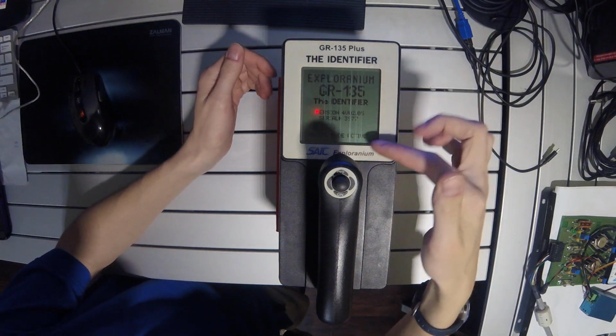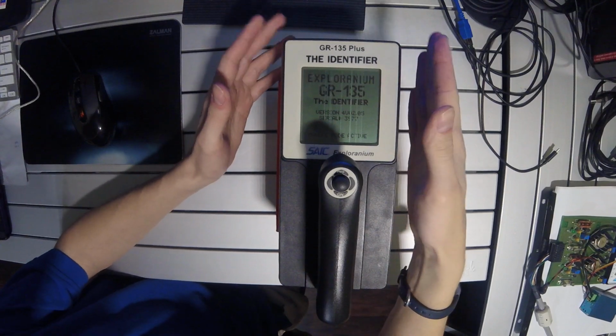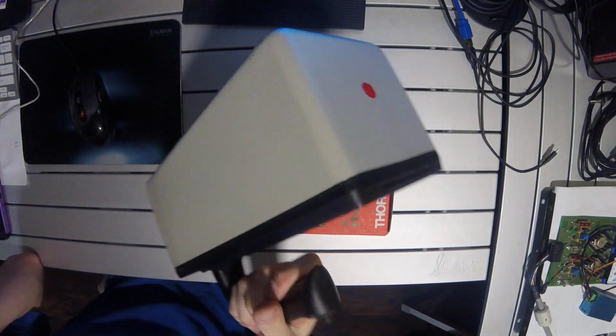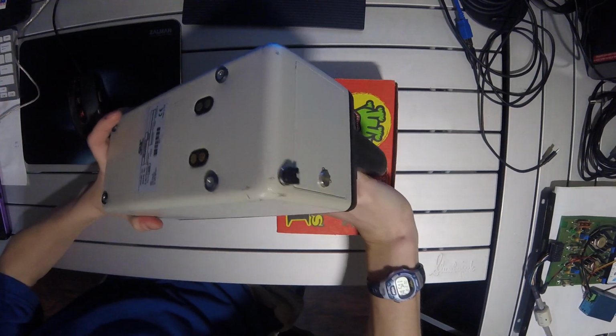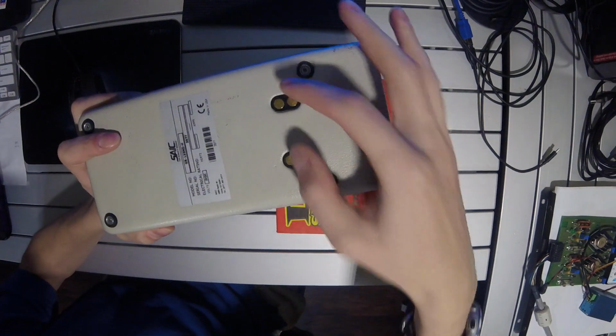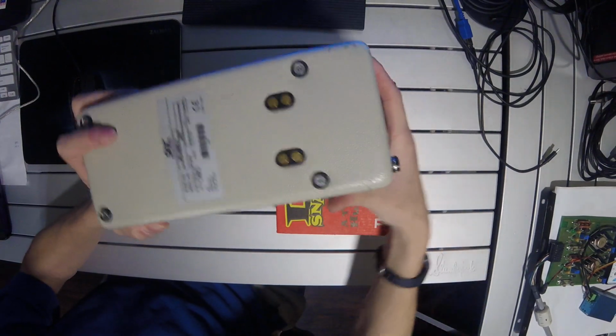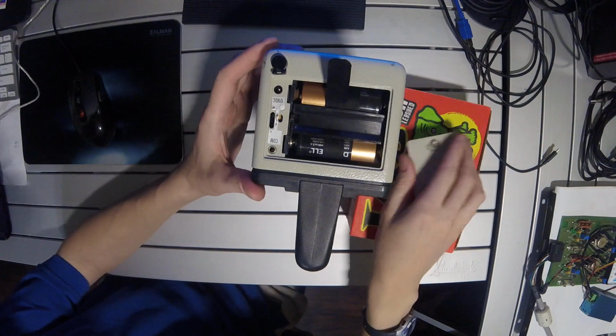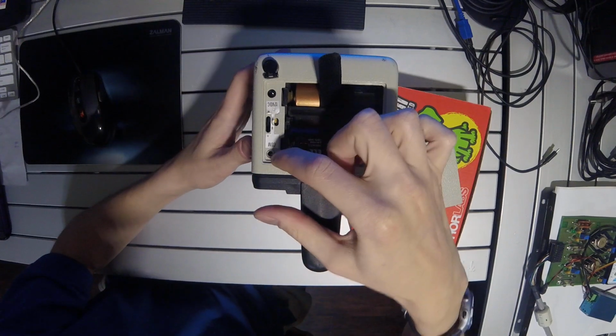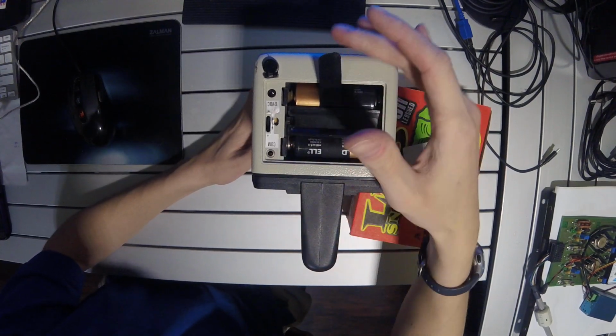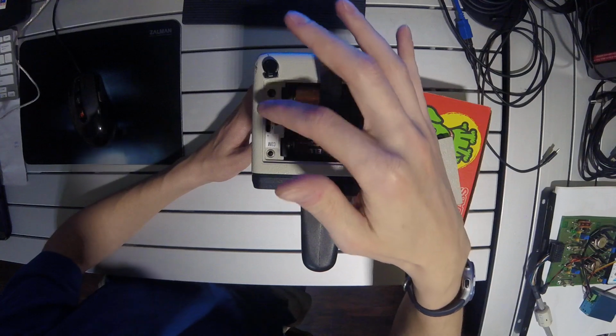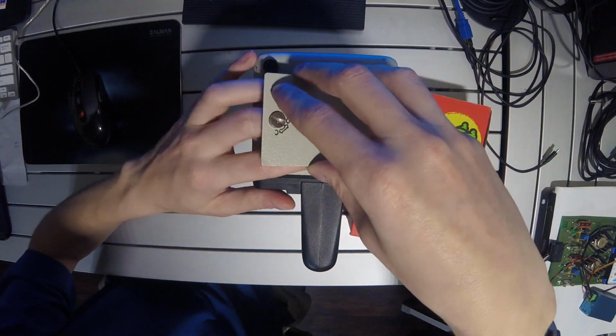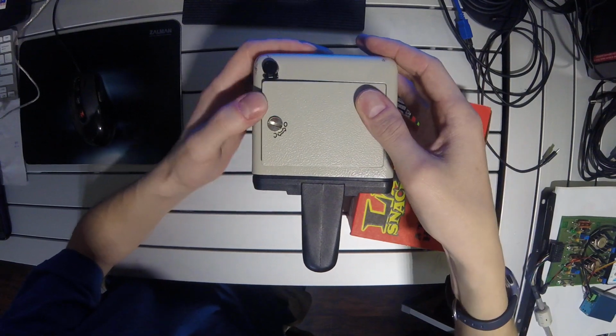As you can see, it has some dead lines, which is common for the older GR-135 units. It's a portable handheld unit, which is ruggedized and battery-powered. It has contacts for a docking cradle for power and serial communications, and it also has a serial communications port in the backpack, in the battery pack. So there's a TRS jack here for plugging in a remote serial port, as well as an external 12 volts DC for external power, and a mode switch for automatic and manual mode. Right now it's set up in manual mode, which gives you access to more of the lower level functionality.